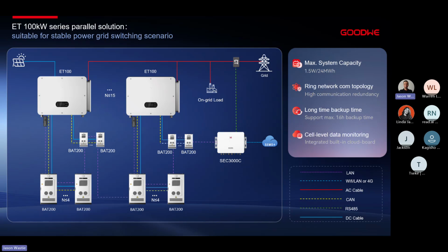For on-grid parallel, we can connect up to 15 inverters together. If we use the BAT 200 series inverter batteries that we will be launching soon, we will be able to connect up to 20 of these inverters in parallel. Reason being is because on the BAT 200 series batteries, we have got additional communication ports, and we can use those to link up more of these inverters together.